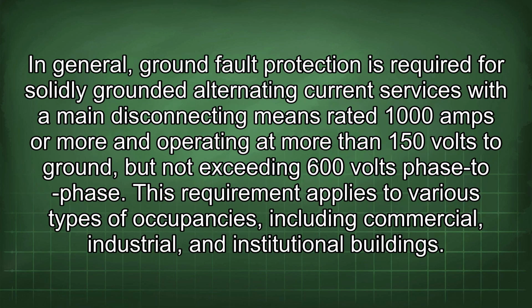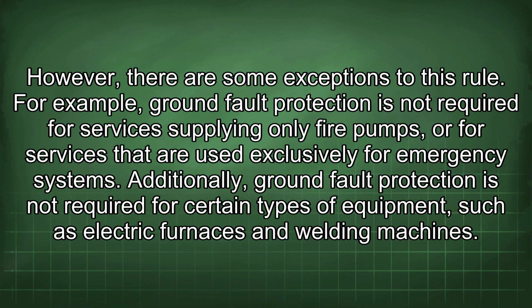In general, ground fault protection is required for solidly grounded alternating current services with the main disconnecting means rated 1000 amps or more and operating at more than 150 volts to ground, but not exceeding 600 volts phase to phase. This requirement applies to various types of occupancies, including commercial, industrial, and institutional buildings. However, there are some exceptions to this rule.